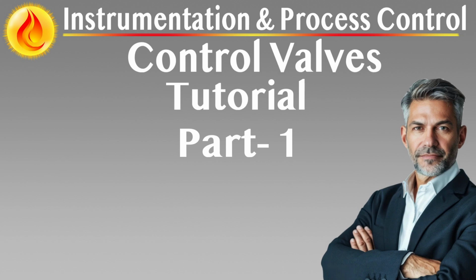All stuffing boxes must feature externally adjustable gland flanges and gland followers. Where valves are shipped with loose glands, clear warning labels must be attached. The gland must be properly set before commissioning.